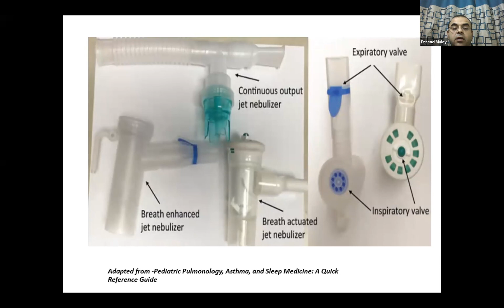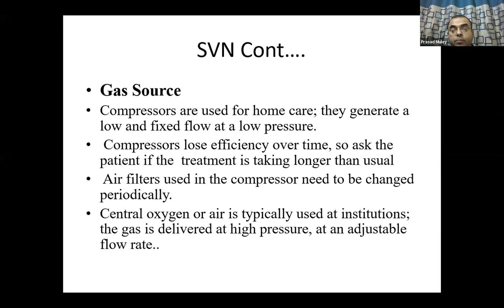So a compressor is used as the gas source for home care, and for hospital care we can use central oxygen. Sometimes the compressor may not work efficiently because the air filters are not working properly. So a compressor has to be maintained properly from time to time, and the air filters in the compressor have to be changed periodically. Tips for patients using a nebulizer: you have to always tell them that tapping should be done as the nebulizer cup level increases during drug delivery. So we have to keep on tapping because some of the mist gets deposited in it.